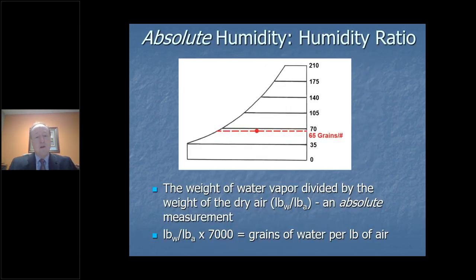But as I mentioned, I prefer that we talk about absolute humidity or the humidity ratio. If you look at the psychrometric chart, now that we have established where the state point is for our particular room, we know that this is 75 degree dry bulb and 62.5 degree wet bulb Fahrenheit, then we can draw that horizontal line through that state point. And if we first think of humidity ratio, that is in terms of grains of moisture per pound of dry air, or we might think of that as pounds of moisture per pound of dry air. If it were pounds per pound, then we multiply that by 7,000 to come up with grains. Grains is just a unit of measurement that we use so that we don't have to deal with all of the small decimals, 0.007 pounds of moisture per pound of dry air or something like that. But again, this is an absolute moisture level.